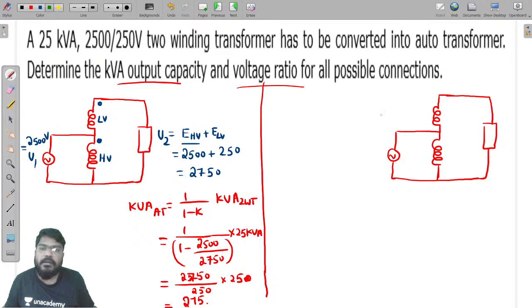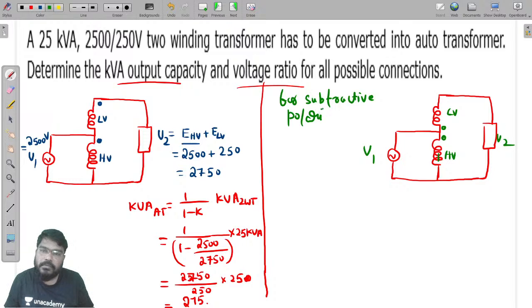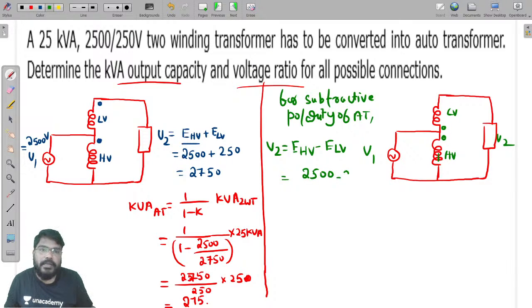So this connection was series additive polarity. Now consider the LV winding and HV winding connected for subtractive polarity of auto transformer. So V2 equals EHV minus ELV, that is 2500 minus 250, equal to 2250 volts. That is a step down auto transformer.